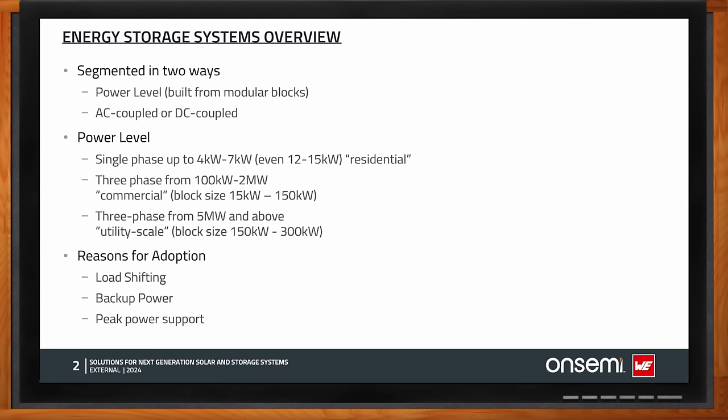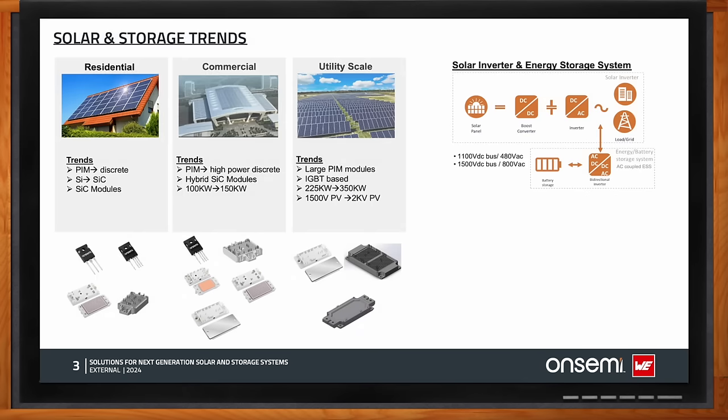What trends are you seeing in the solar and storage arenas? There are two segments based on power level and isolation — AC coupled or DC coupled. Residential applications run from 4 to 15 kilowatts; commercial from 100 kilowatts to 2 megawatts with building blocks of 15 to 150 kilowatts; and utility three-phase systems from 5 megawatts and above with building blocks of 225 to 350 kilowatts. Notably, the DC bus used to be 1100 volts for utility systems but is now moving to 1500 volts, necessitating 2 kilovolt power modules.